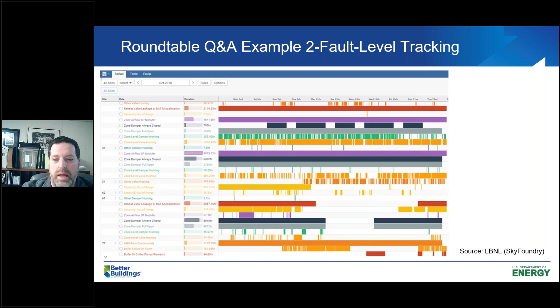This shows the frequency of the fault and tracks it over time, so you can potentially see repeat occurrences. Looking in the middle, that red is the reheat valve leakage or DAT miscalibration. It looks seasonal, not occurring for certain months, so it probably was never corrected, but also changes with weather and other operational changes. So just because it looked closed here, it's occurring again — this could either be a continuation of it or a repeat one. It would probably require a little more digging to find out.